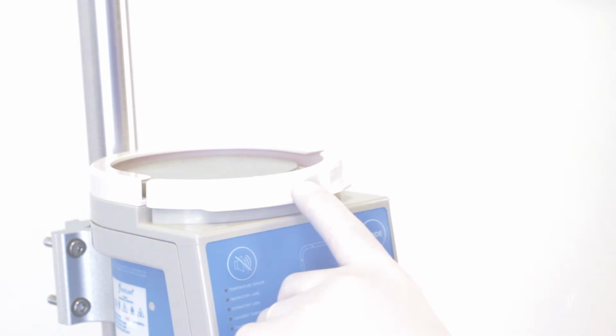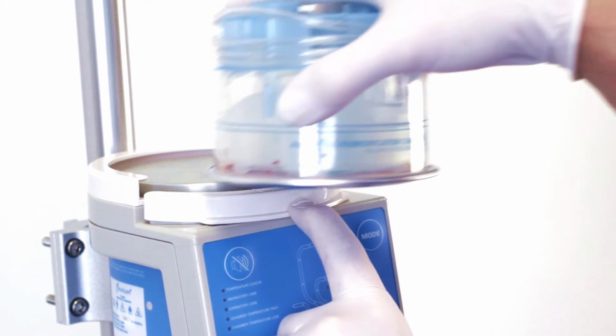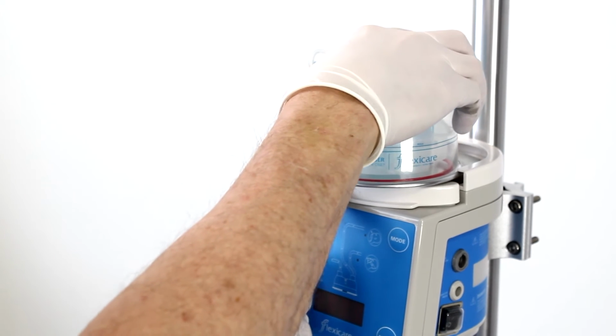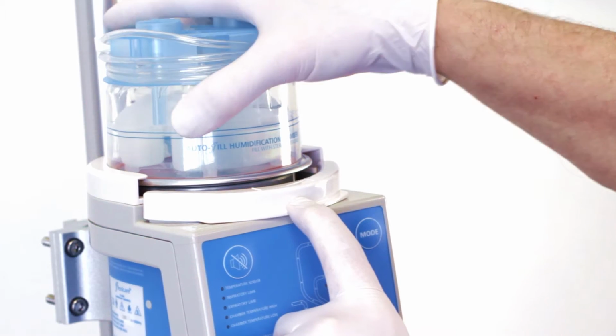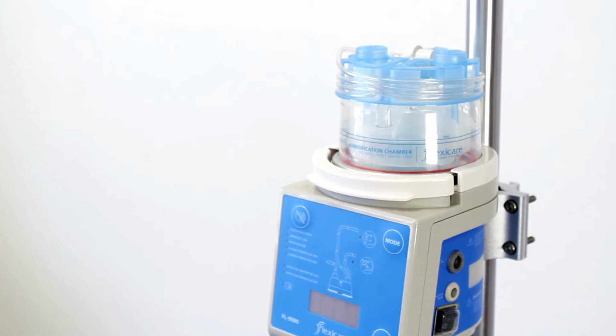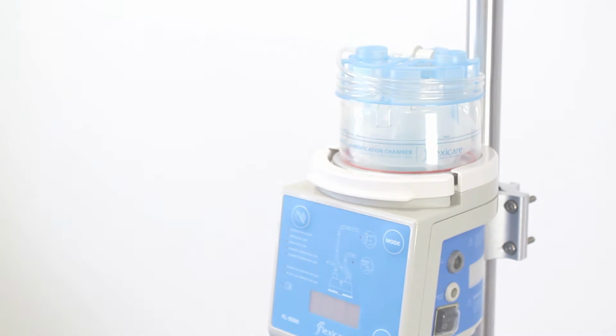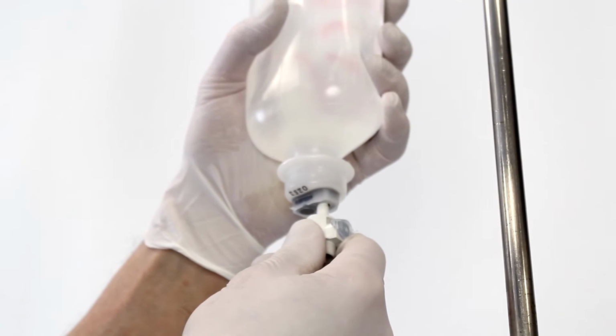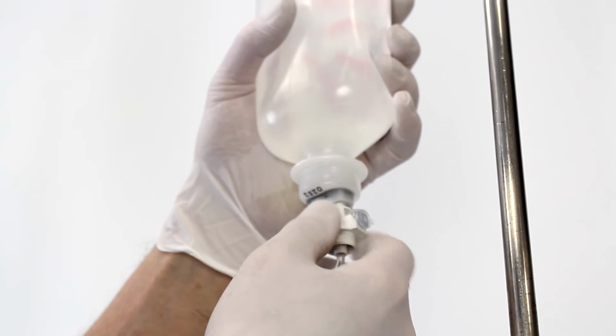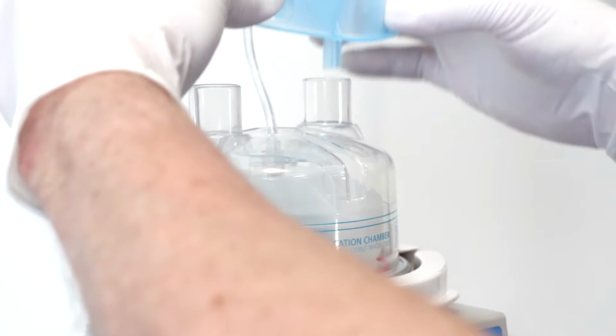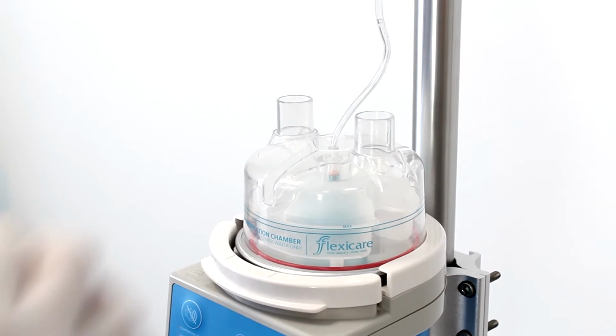The humidification chamber is fitted to the heater plate by applying downward pressure on the spring-loaded front guard, sliding the chamber into position and then releasing the guard to lock the chamber in place. Unravel the delivery set and attach to the sterile water bag or bottle using the vented spike. The pinch clamp should be closed. Remove the protective cover from the humidification chamber and discard.